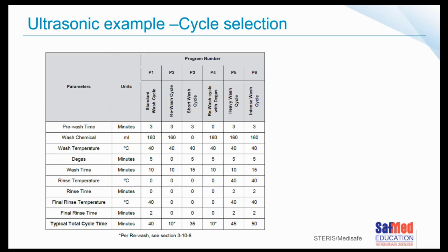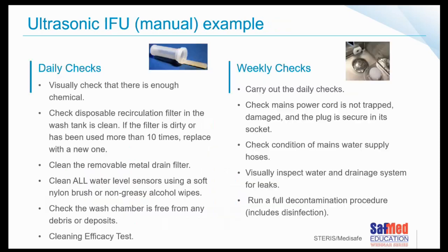The wash time, many times you can adjust that wash time. You can use the preset settings, or you can adjust it. Remember, you might adjust it based on the instructions for use from the manufacturer. What the rinse temperature might be, what the rinse time is, the final rinse, everything like that. So it can give you an idea of what it is you need, and hopefully your ultrasonic cleaner gives you those options. Again, some examples from a manual of the type of checks that you may need to carry out. This, of course, is going to be dependent on your make and model, but here are some examples.